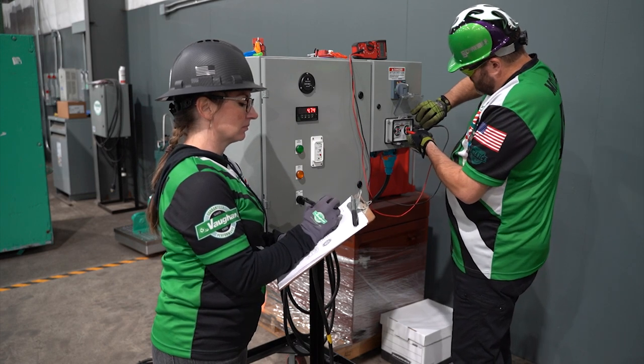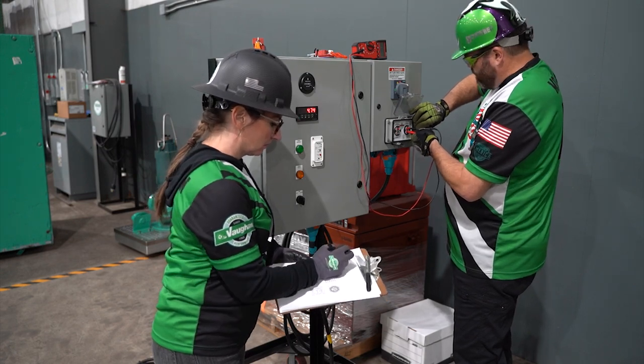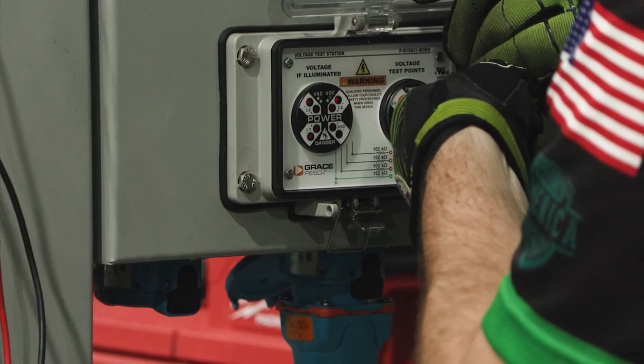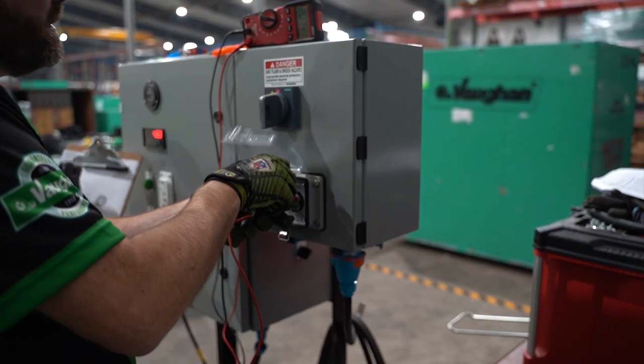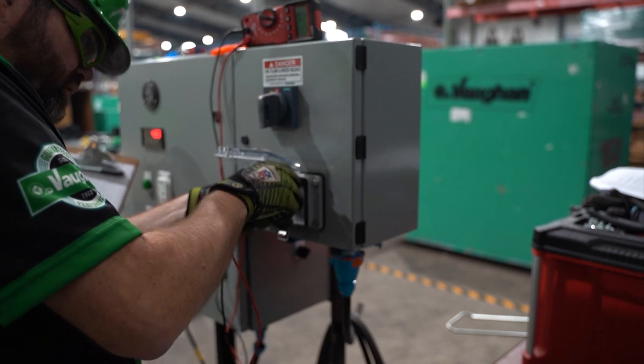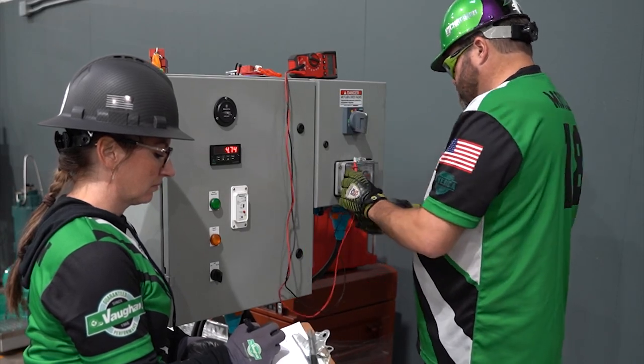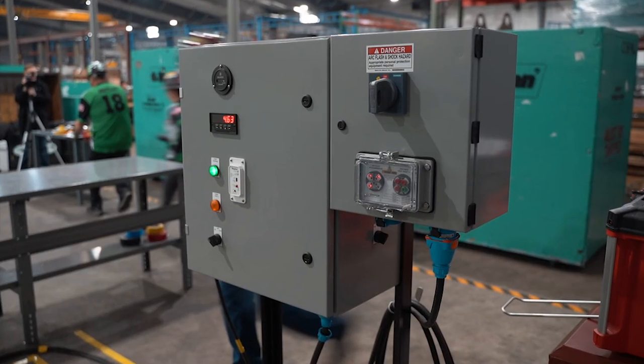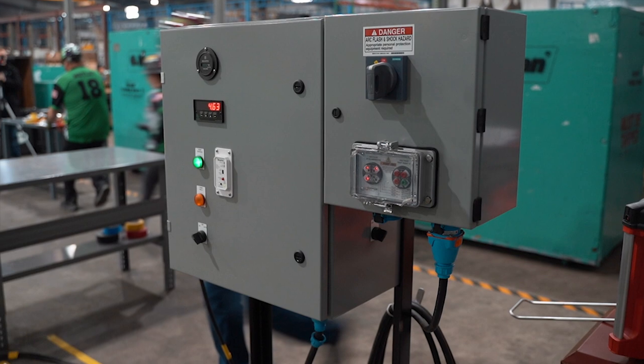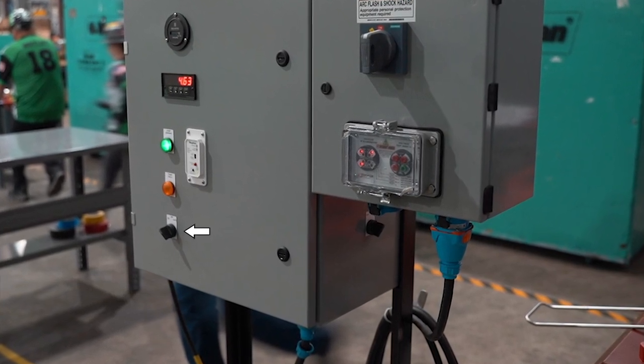Check voltage between leg two and leg three, verbalize 'leg two, leg three, voltage present,' and record voltage on sheet. Check voltage between leg one and leg three, verbalize 'leg one, leg three, voltage present,' and record voltage on sheet.